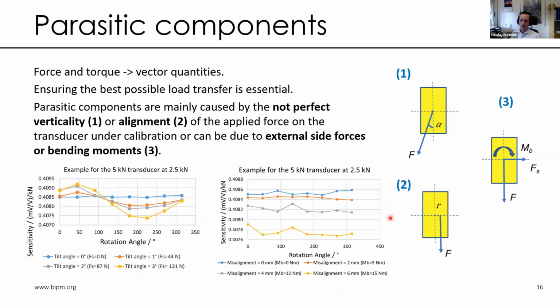For alignment, you can misalign the transducer, move it away from the axis, and see that the farther away you are from the axis, the more the sensitivity of the force transducer drops. So it's very important to verify that you are measuring in a good position. You have to mount the transducer so that its own axis matches the axis of force or torque generation.